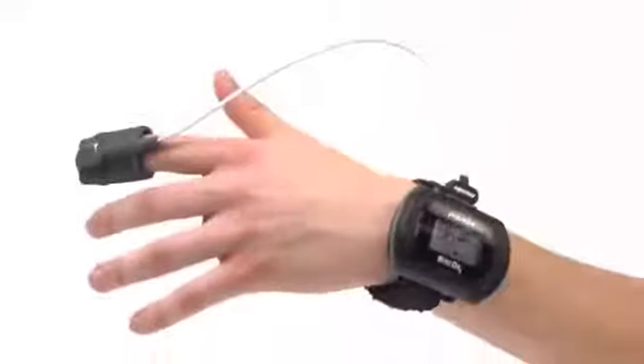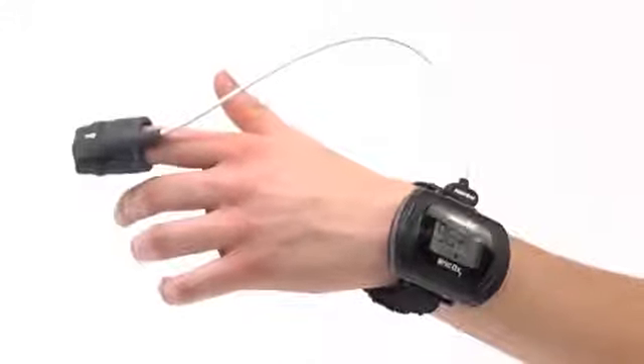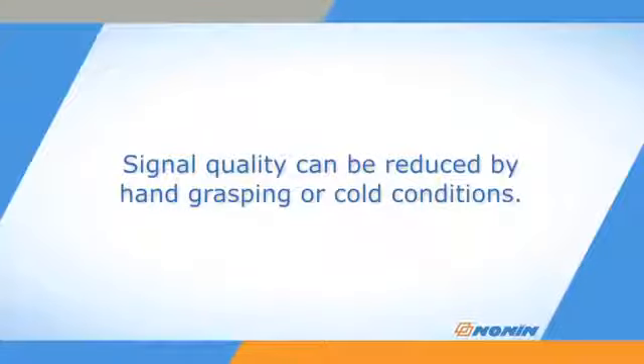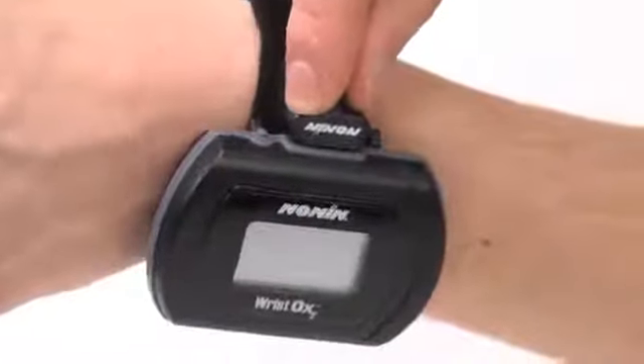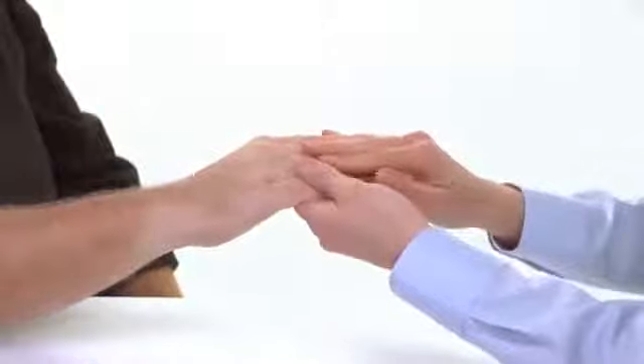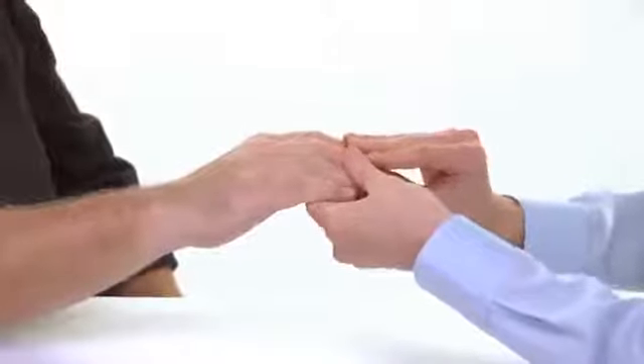Signal loss from the sensor is possible with significant hand or body movements or disconnection of the cable. Signal quality can also be reduced by hand grasping or cold conditions too, which may reduce blood flow. Check and correct the position of the sensor if you see reduced pulse signal quality. If the hand has been grasping or it is cold, relax and warm the hand.